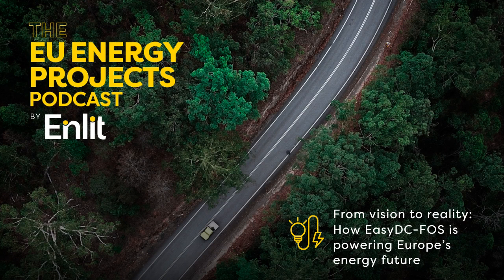For HVDC, I'd say the main challenges we have for the project are, first, the environmental impact of XLPE. If you want to go higher in power and in power loads on the actual designs, you would have to move, for example, to have a 2 gigawatt capacity on a cable, beyond 525 kV, probably to 700 kV and above, to operate that asset safely.